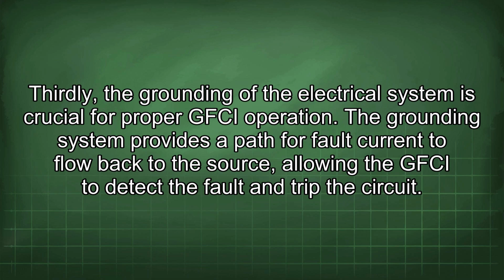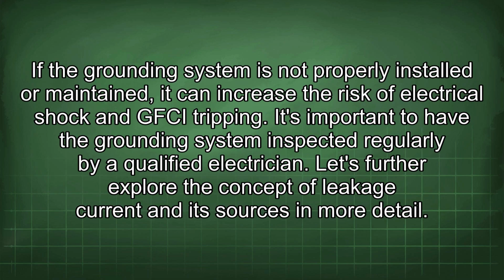Thirdly, the grounding of the electrical system is crucial for proper GFCI operation. The grounding system provides a path for fault current to flow back to the source, allowing the GFCI to detect the fault and trip the circuit. If the grounding system is not properly installed or maintained, it can increase the risk of electrical shock and GFCI tripping. It's important to have the grounding system inspected regularly by a qualified electrician.